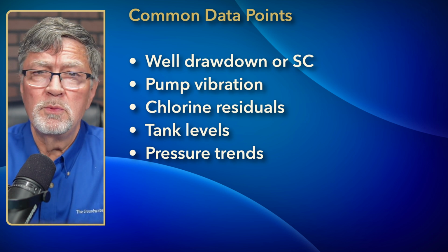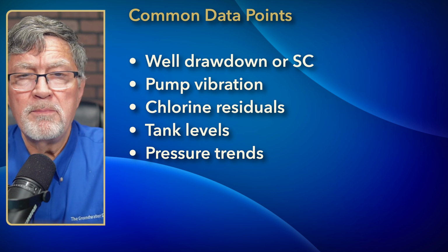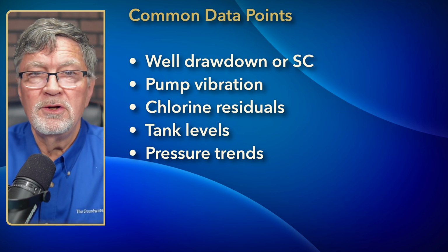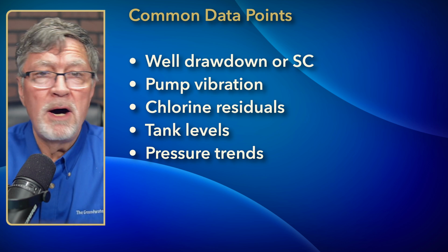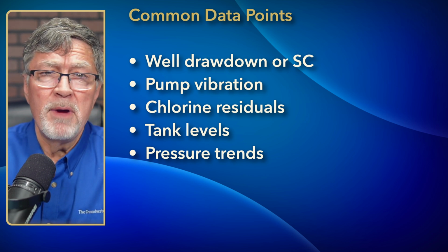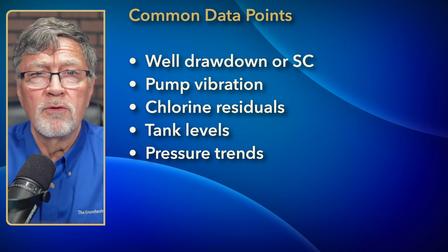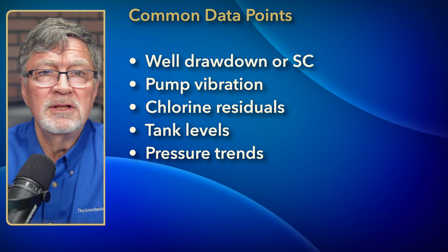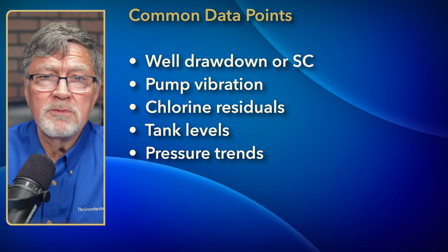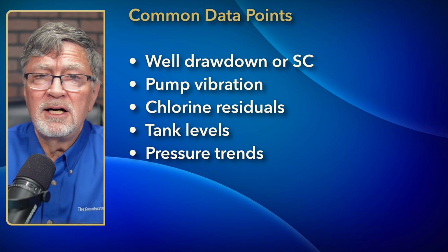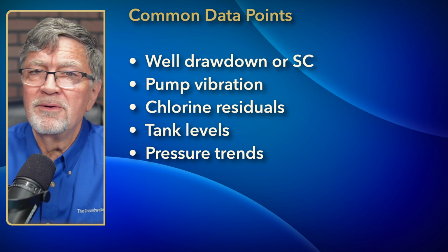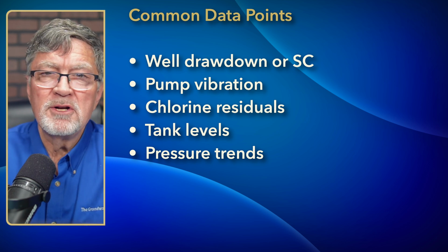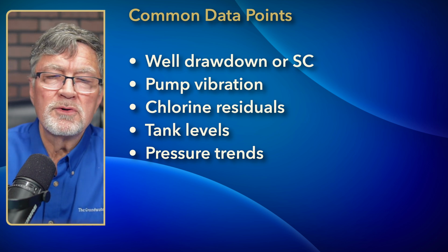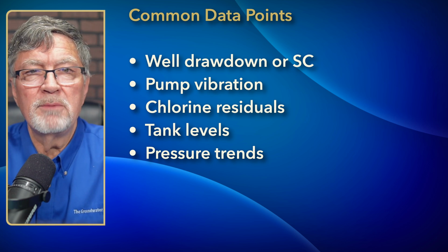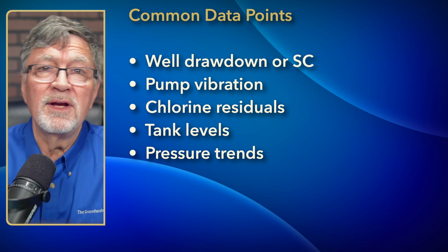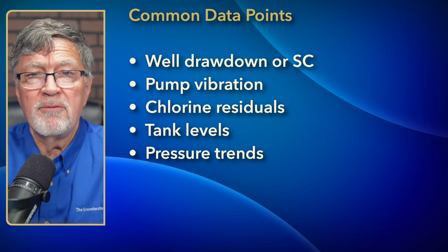Some examples would be well drawdown or specific capacity, which tells you when you need to rehab your well. Pump vibration is one way you can tell if your bearings are going out and you may need to overhaul the pump — that's especially true on line shaft turbine pumps. Chlorine residuals and your chemical feed sometimes go out of calibration or go out of whack, so seeing how much variation you have there, tank levels, and pressure trends at the pumps are all things to track, and they can tell you when you're starting to have problems.